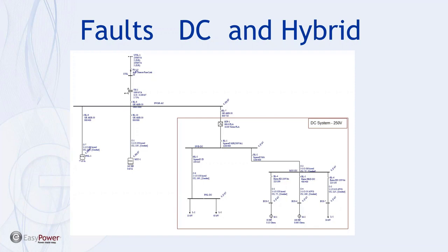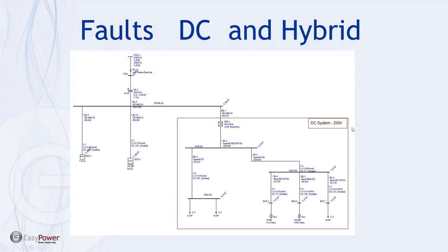So one other condition in terms of controlling of the fault current time is the thyristor blocking under fault conditions, which you would find or we would find in the rectifier. Most likely a thyristor device will stop firing when it senses a short circuit condition. And this time is set up by the manufacturers and may be a software or hardware related parameter. And so this detail is typically left for detailed transient simulations. So under conditions of a DC bus fault, most likely the current limiting fuses, typically in series with each of the thyristors would be the limiting factor. So given that the bridges can have both series and parallel combinations, it pretty much is dependent upon what the manufacturer's data sheet says for overload cutoff that we have to rely on. So let's jump into EasyPower and see how all this stuff looks.